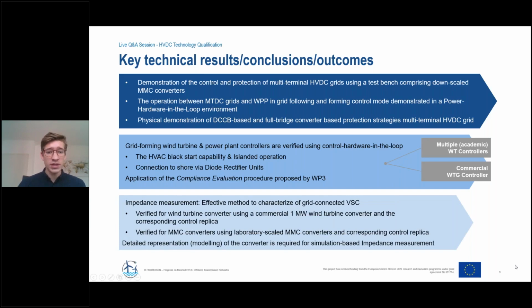For the stability assessment, our main conclusion was that the developed impedance measurement method worked very well. We verified it by measuring and comparing the impedance of a real wind turbine converter, the same one used in the previous case—the commercial wind turbine converter of 1 megawatt—compared with its control replica.